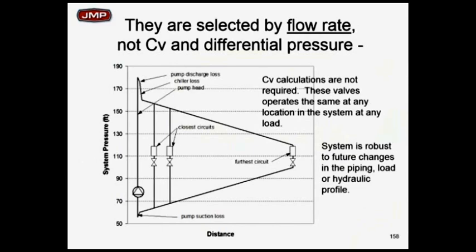You should be picking these valves on what? Every two-way valve here should be picked on CV. Every two-way valve here should be picked on authority and pressure drop available. You should run a detailed head loss calculation on every circuit on that campus for 1,000 valves and make the right valve authority and the right CV for every two-way valve on that campus. That's not quite practical, you said. I'd agree with you, it's not. But you can do it. In theory, you can do that. But every time you change out a valve on the campus, you got to look at all the other 1,000 valves that are still there and make sure they got the right pressure drop.